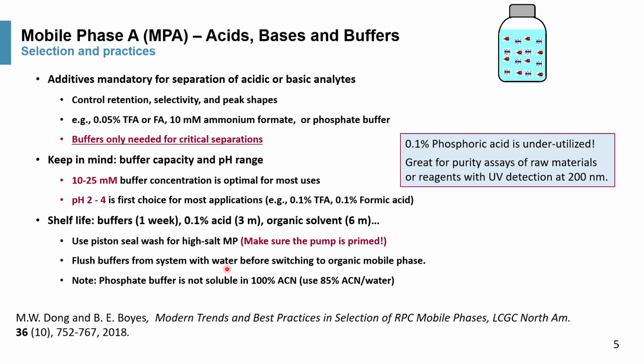Some applications of ion exchange require the piston seal wash to wash the salt off the back of the piston under high salt mobile phase conditions. In those cases, make sure that the peristaltic pump that feeds the piston wash solution is primed. We mentioned a couple of times that buffer should not stay in the system when it's not running, and you should rinse it out with water before switching to organic mobile phases. A very strong note of caution: phosphate buffer, particularly at high concentrations such as 50 millimolar, is not soluble in 100% acetonitrile. You should use no more than 85% acetonitrile in water if you want to mix it directly.